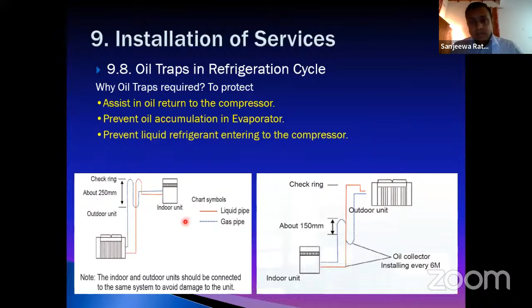oil traps. If it is an air-cooled system, especially air-cooled package units, it's very vital, very important to install these oil traps. If the height difference between the indoor and outdoor units is considerable, say for example more than 10 meters, it is a must to install these oil traps in order to prevent damage to the compressors, because they can be damaged without oil. If oil transfers to the indoor unit, and the oil traps are not sized properly or not installed properly, then the oil will not return to the compressor, resulting in seizure of the compressors.